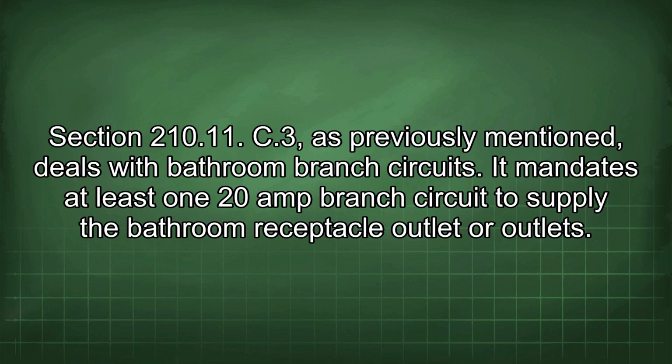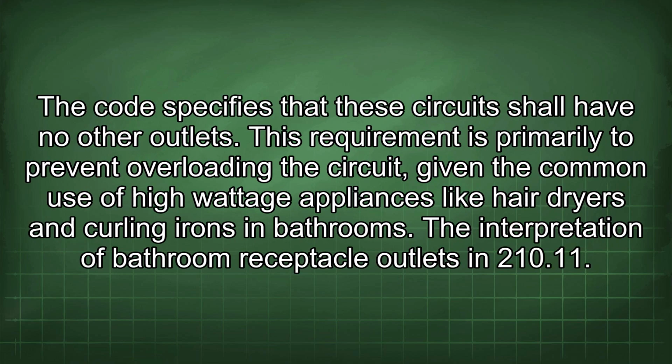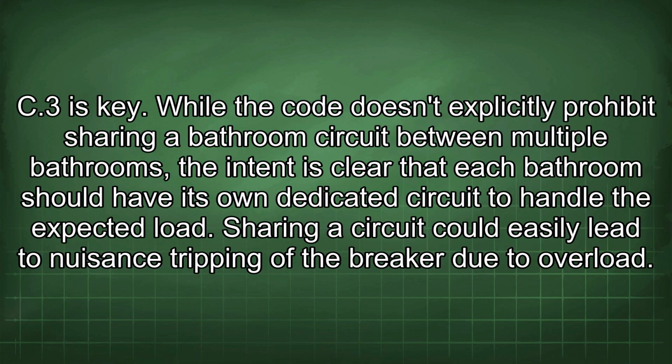It mandates at least one 20-amp branch circuit to supply the bathroom receptacle outlet or outlets. The code specifies that these circuits shall have no other outlets. This requirement is primarily to prevent overloading the circuit, given the common use of high-wattage appliances like hairdryers and curling irons in bathrooms. The interpretation of bathroom receptacle outlets in 210.11 C3 is key.